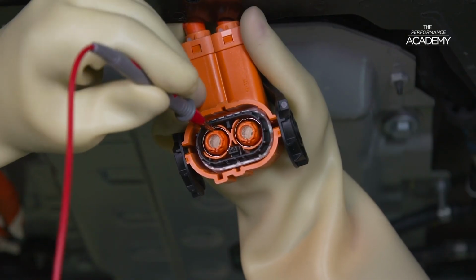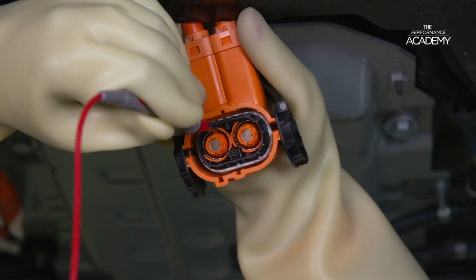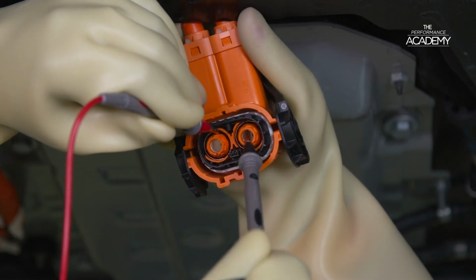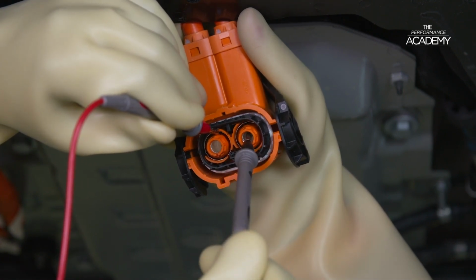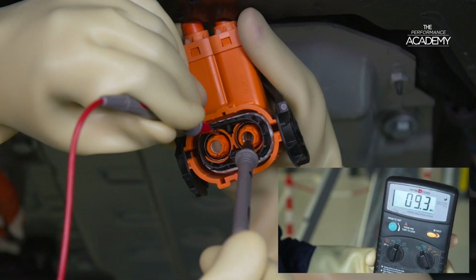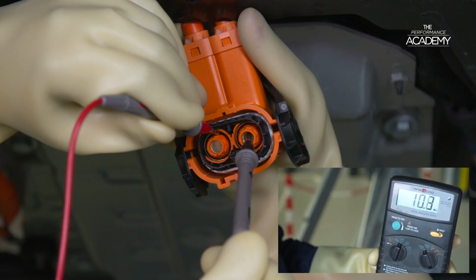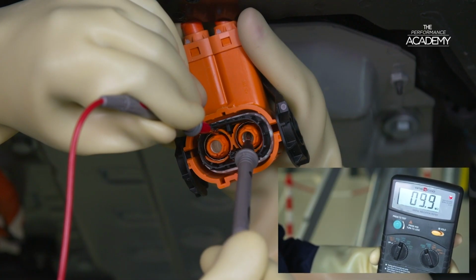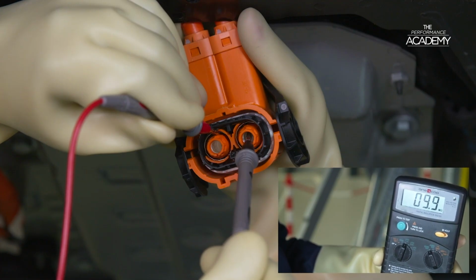We then repeat the process for the other pin on the connector, testing the resistance value between the high voltage central pin and the opposite earth screen. Put the negative probe on the earth at E of the electrical power circuit connector. Put the positive probe on the pin at F of the electrical power circuit connector and check that the resistance value is higher than the threshold 2 megaohms stated.